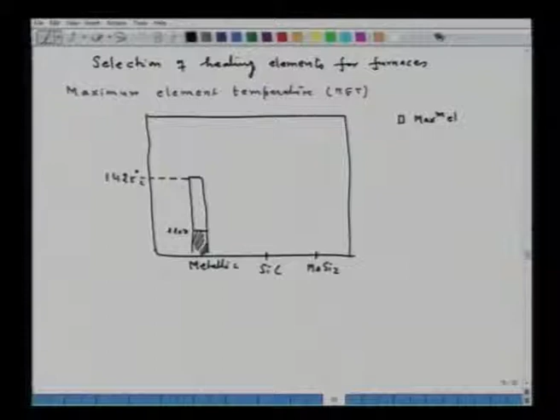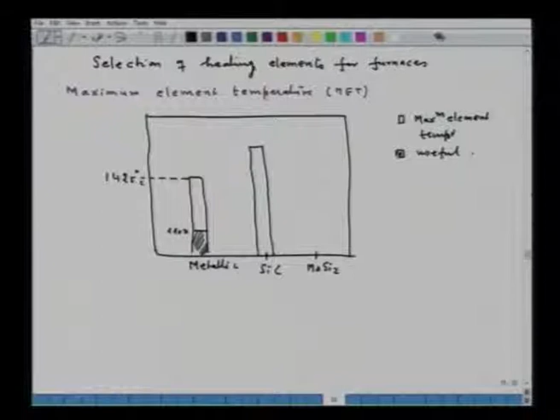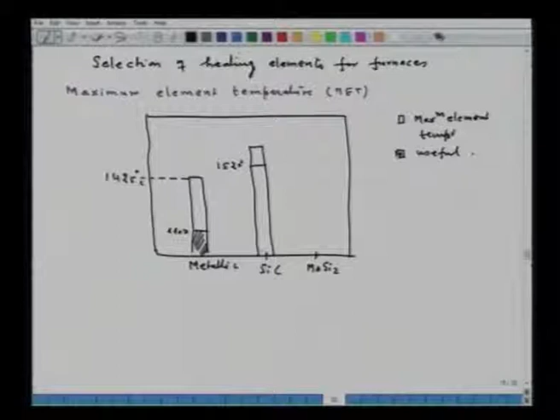Now, similarly, if I consider silicon carbide, this is for the silicon carbide, and silicon carbide can be safely used up to 1520 degrees Celsius, whereas the maximum element temperature is 1650 degrees Celsius. Then if I take molybdenum disilicide, this temperature is around 1700 degrees Celsius and this temperature is around 1820 degrees Celsius. So, this is the information about the maximum element temperature, that is one thing we require.